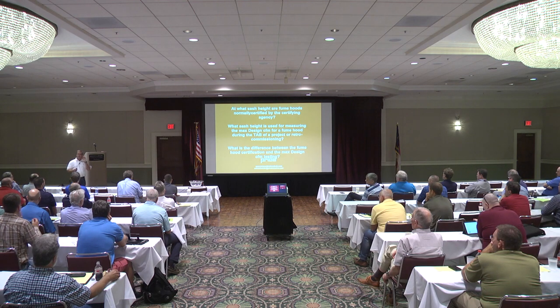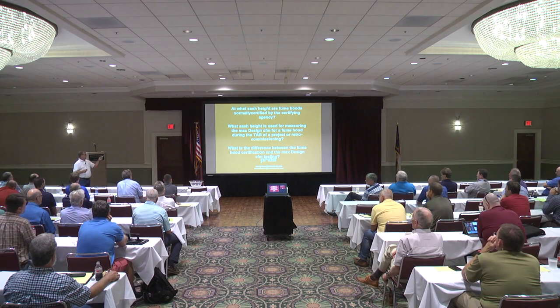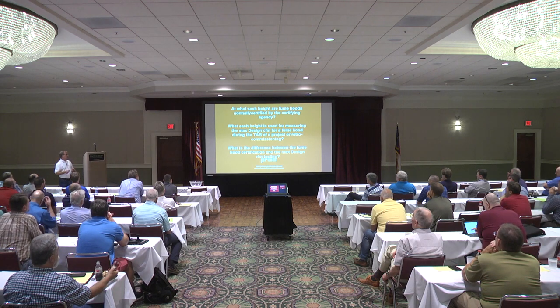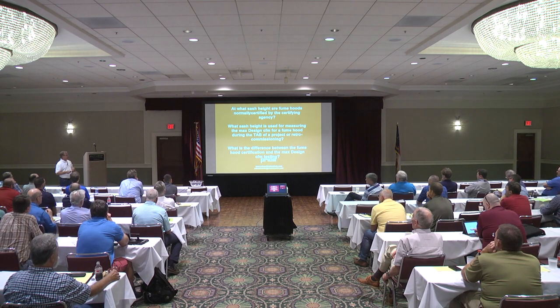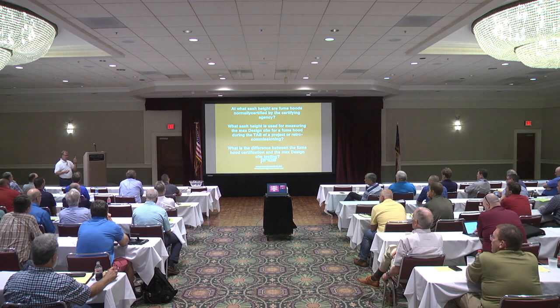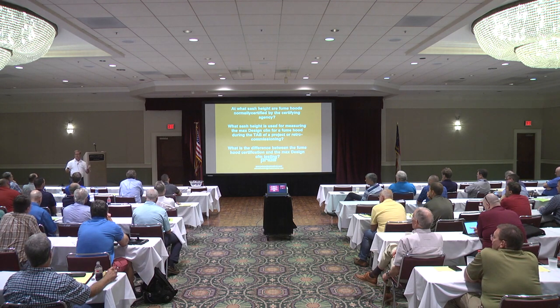What sash height? Come on, most of y'all want to say 18. I know it because I see it all the time. So the question is, what is the difference between the fume hood certification and the max design CFM testing? So we said the fume hood certifier has one job, and that's to check the fume hood at 18 inches. Somebody came up with that number.